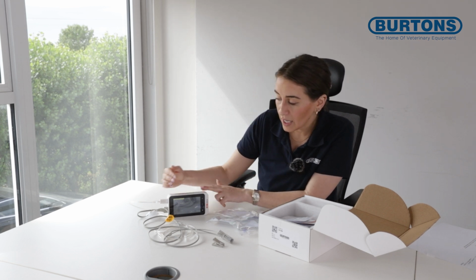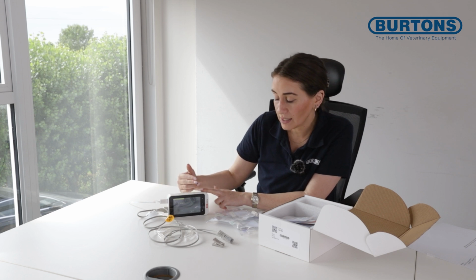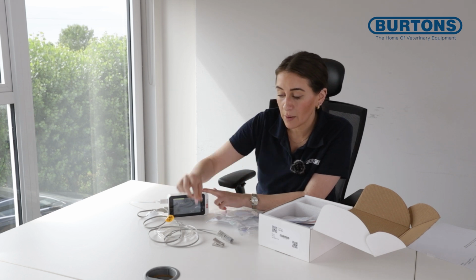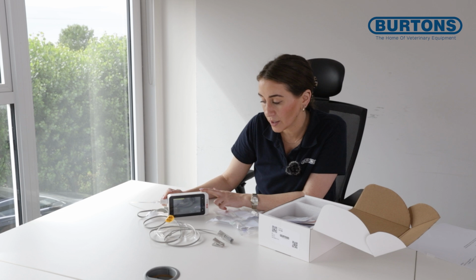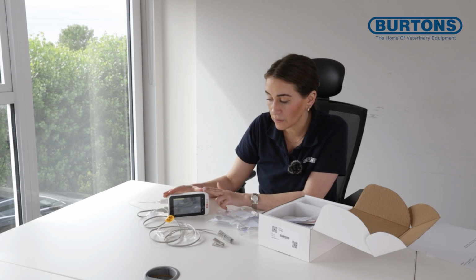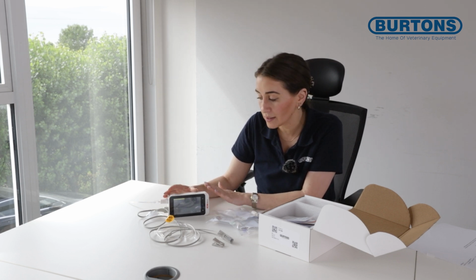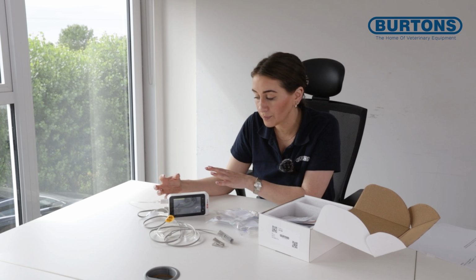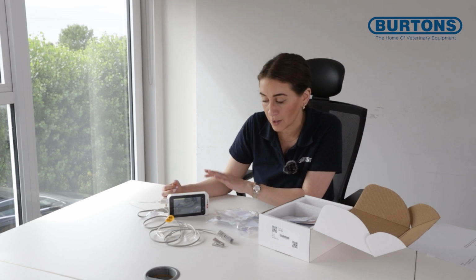If you have a scenario where the CO2 module is not working adequately and we've changed the sample line and changed the filter, beyond that is a case of going to the repair centre here at Burton's for an inspection to hopefully repair the internal module that might be damaged.